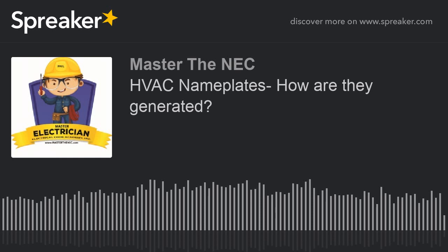Okay, so let's do a scenario. What if you come across and you see a nameplate that says minimum circuit ampacity of 18 amps, maximum overcurrent protection of 40 amps, and you're sitting there going, there's no way that I'm going to choose, for example, a 12 conductor for 20 amps, and here I am in a situation where I am going to potentially protect that with a 40 amp breaker. And you're like, this just doesn't sound right, because right here in 240.4(D), it says that a 12 gauge has to be protected with a 20 amp overcurrent device.